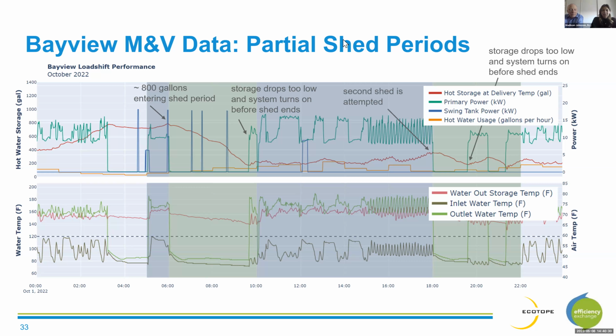And I think there's 3 main takeaways from this. Takeaway number 1 is that despite us not completing the entire shed period, we're still able to shift a significant portion of that energy use outside of the peak demand period, which we would consider pretty successful. The second takeaway would be that the system did have enough capacity to be able to handle the load. We didn't require any backup electric resistance heating here, and the system was able to recover from this partial shed period. However, we could have used a little bit more capacity to be able to load up for that second shed period. And then the third takeaway, and arguably the most important, is that despite our stress on the system, we were always guaranteeing the tenants access to hot water. So there was no disruption to them through this experimentation.